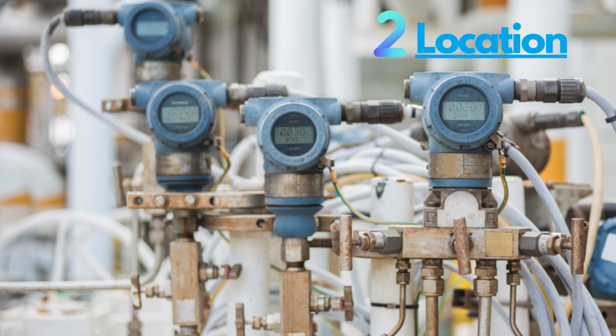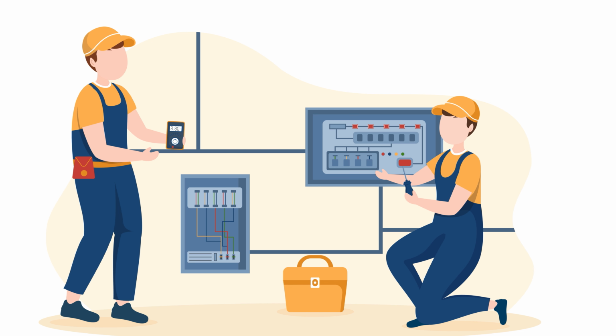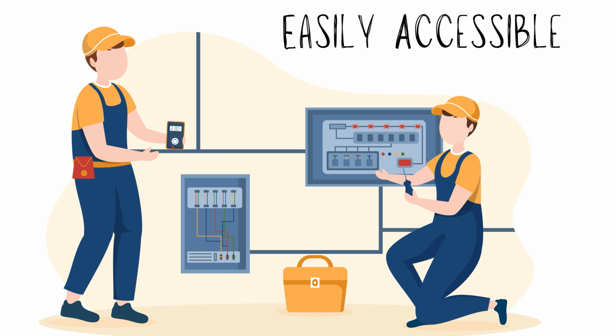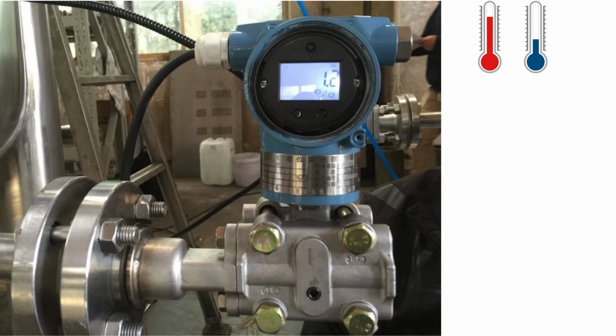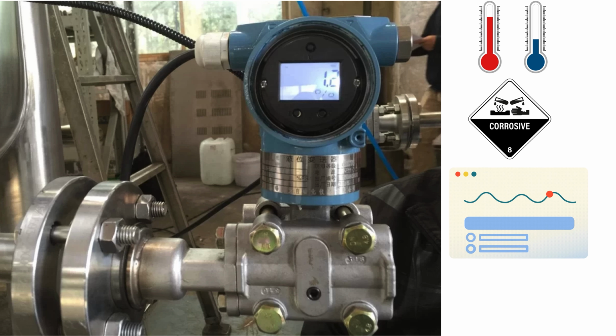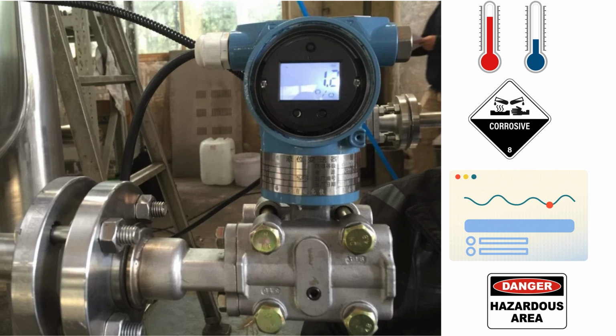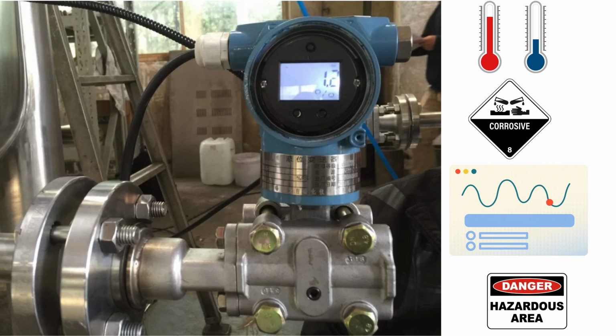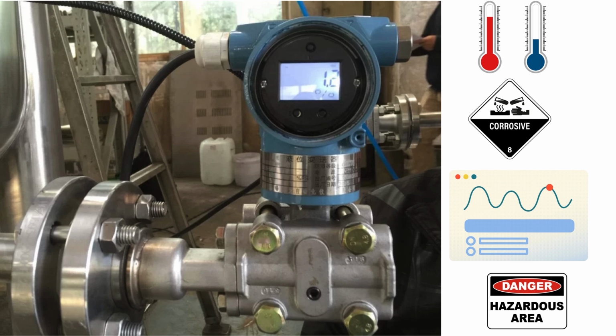Step 2. Location selection. First, choose the right location for your transmitter. The following points should be considered when selecting an installation location. Ensure it's easily accessible for maintenance. Avoid locations subject to wide temperature variations or a significant temperature gradient. Avoid installing the transmitter in a corrosive atmosphere. Select an installation site suffering minimum shock and vibration. Explosion-protected transmitters can be installed in hazardous areas according to the types of gases for which they are certified.